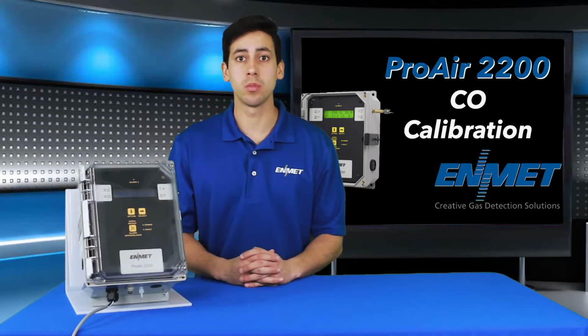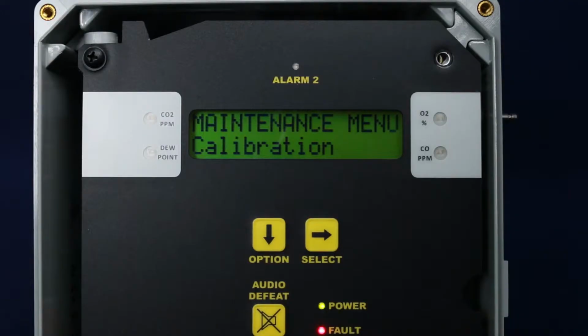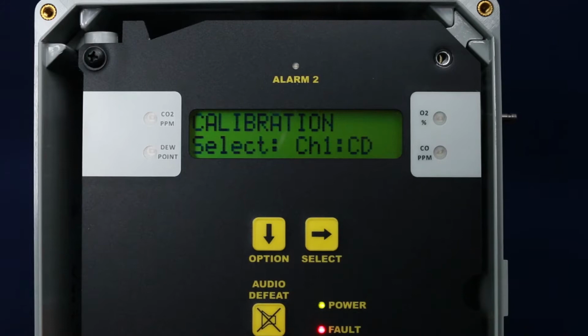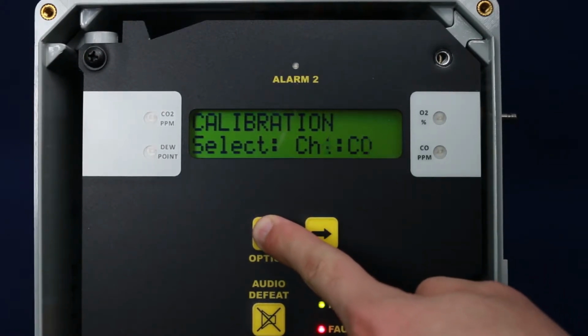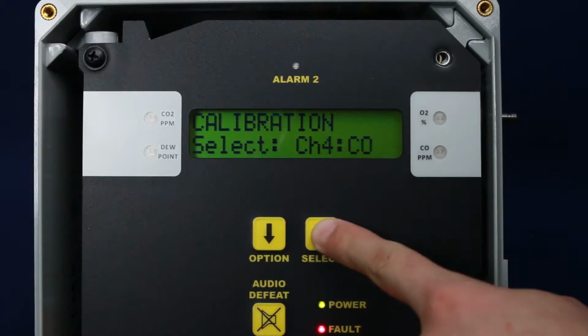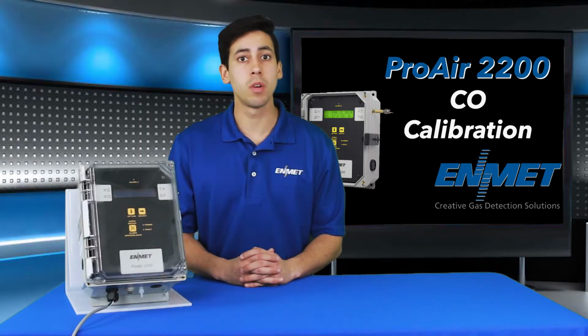Once you enter the password, the calibration submenu option will be displayed. To enter this, you need to press Select. Cycle through the channels using the Option key until the CO channel is displayed. Press Select to enter the CO calibration mode. At this point, you are in the ProAir CO calibration mode. After pressing the Select button, you will see LoCal on the bottom row of the display.